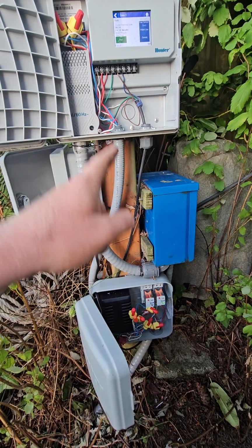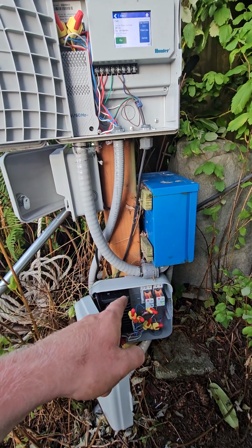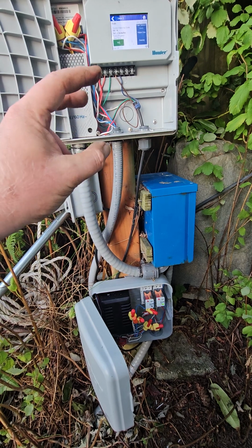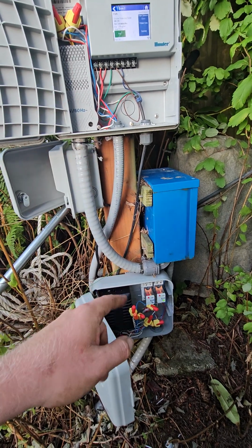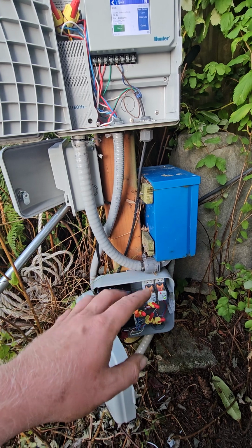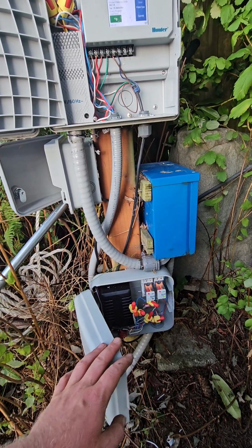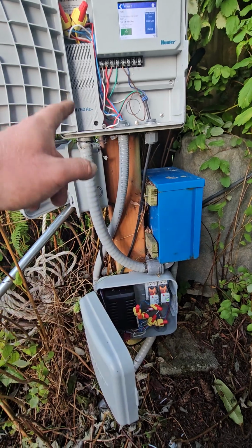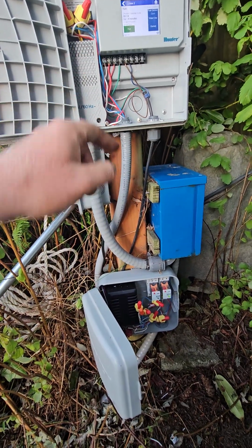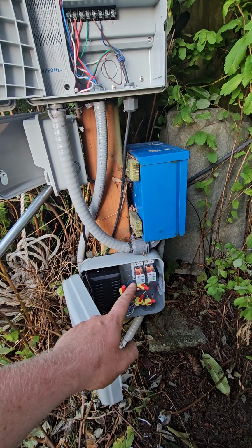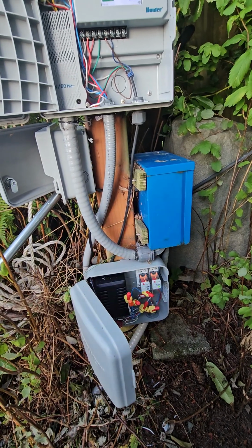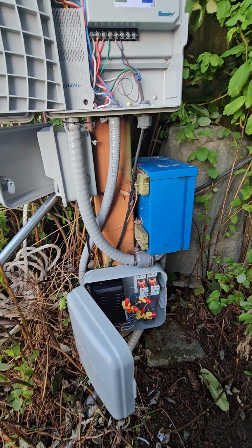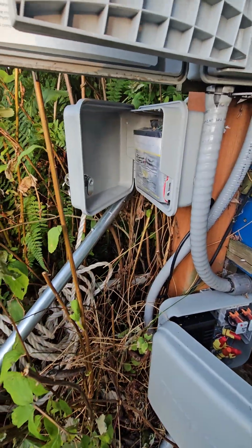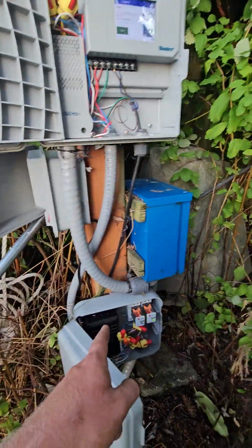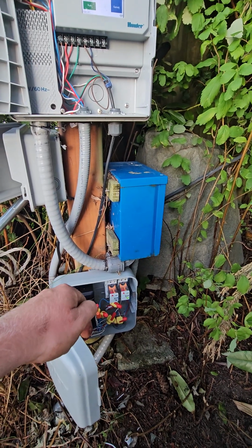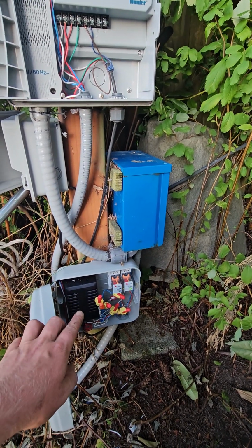The controller will still be on because it'll go onto UPS power, but we'll have a sensor set up that basically tells us fuse blown, and then it tells us this thing stops working entirely. At least we have some idea of what might have happened to it. So basically, like I said, power in, power back, and then output power that actually powers the controller. And we aren't using this relay, so this power is basically getting redirected right to the 24 volt coil of the contactor. We had a little Duracell battery, but we're running just a lantern battery in there, so that comes in 12 volt input into the UPS.